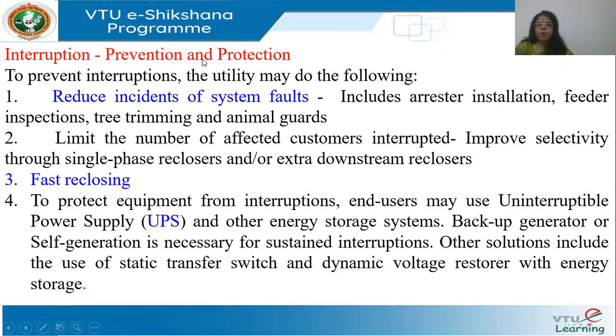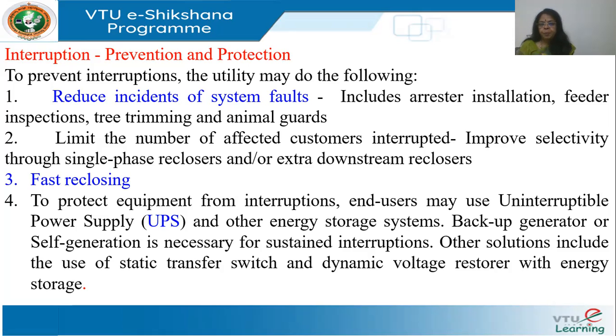To prevent and protect against interruptions: reduce the incidence of system faults by including surge arrestors, inspecting feeders, doing tree trimming to reduce short circuits, and installing animal guards. Try to limit the number of users affected — improve selectivity so that if one line goes out, only a localized set of customers is impacted.